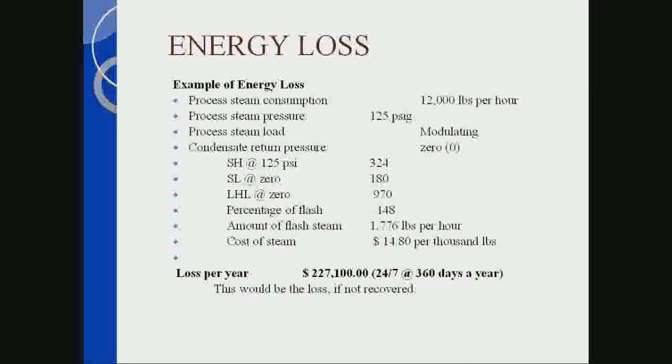I go to the saturated steam table. I find SH equals 324 BTU per pound. SL equals 180 BTU per pound. LHL equals 970 BTU per pound. The percentage of the flash, 0.148. The amount of flash that is going to occur is 1,776 pounds per hour.